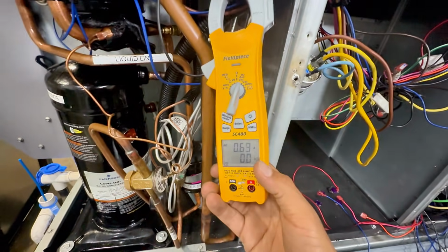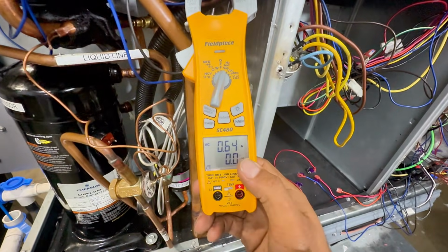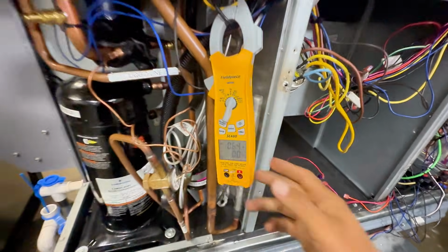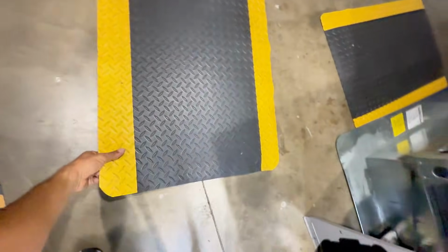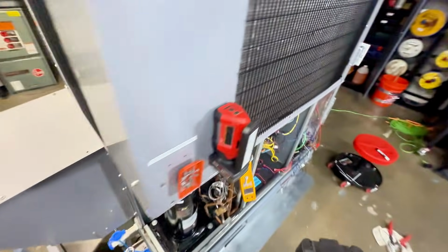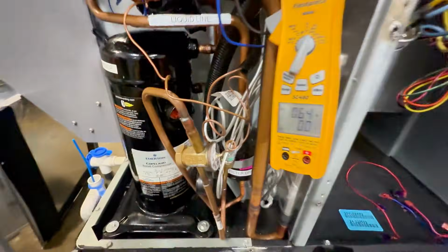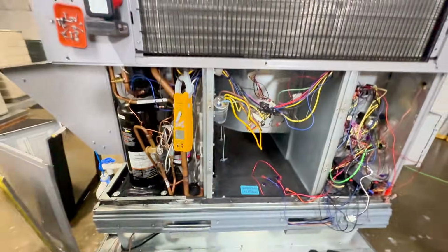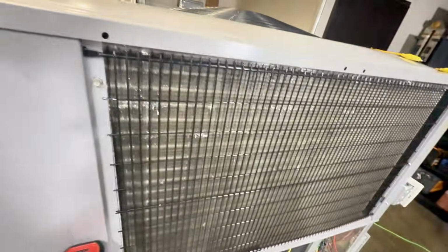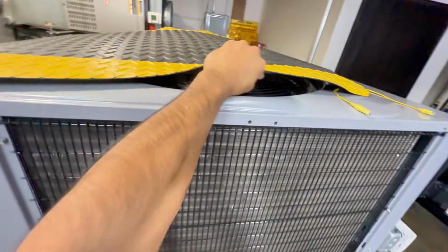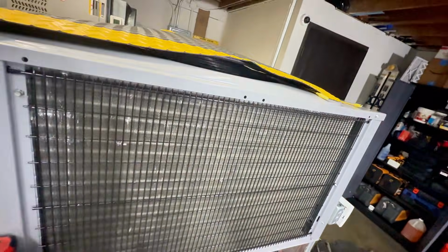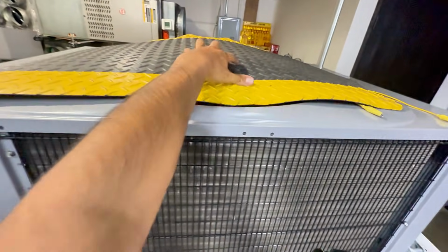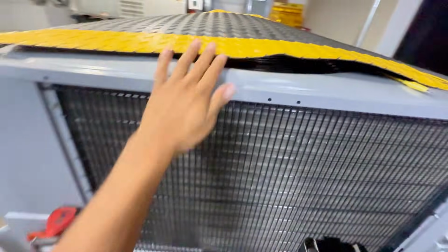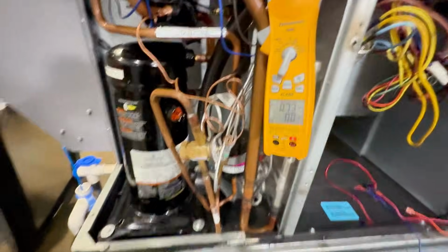Now this is good for troubleshooting because of this reason. Look what I'm gonna do. That number there is gonna change once I do this. I'm gonna go ahead and get this mat that I had ready, okay? So let's say you have a dirty condenser. 0.64, it's good. But let's say you have a dirty condenser, okay? So let's go ahead and put this over that, okay? All right. Dirty condenser, it's not too much of a restriction. It is pretty bad, but air is still coming out, but there's a restriction. Look at that right there.